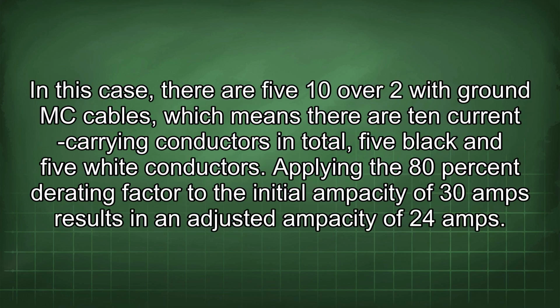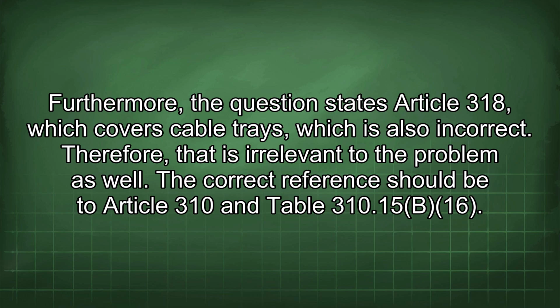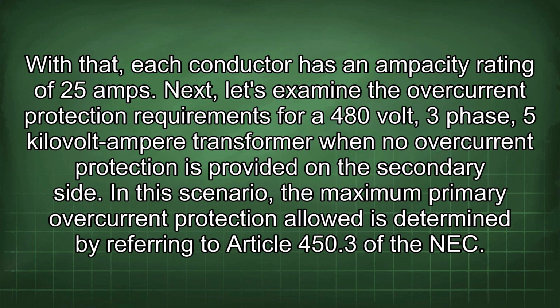In this case, there are 5 10/2 with ground MC cables, which means there are 10 current carrying conductors in total, 5 black and 5 white conductors. Applying the 80% derating factor to the initial ampacity of 30 amps results in an adjusted ampacity of 24 amps. Furthermore, the question states Article 318, which covers cable trays, which is also incorrect. Therefore, that is irrelevant to the problem as well. The correct reference should be to Article 310 and Table 310.15(B)(16). With that, each conductor has an ampacity rating of 25 amps.